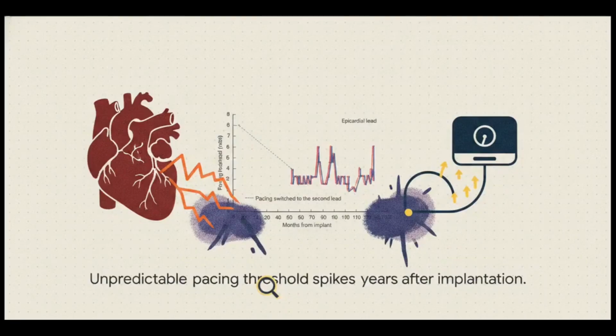You also need to notice the hidden danger lurking years after surgery on this graph. Ideally, you want that threshold line to stay low and flat. But look at these massive, totally unpredictable spikes occurring 70 or 100 months post-implant. Over time, fibrotic scar tissue can build up exactly where the wire meets the heart, suddenly increasing the electrical resistance. If the pacemaker isn't programmed to deliver a high enough voltage to overcome this new spike in resistance, the heart won't capture the signal. This loss of pacing can absolutely cause sudden death. This is exactly why patients require lifelong routine medical surveillance to constantly check and adjust these life-saving devices. It's not just a set-it-and-forget-it surgery.